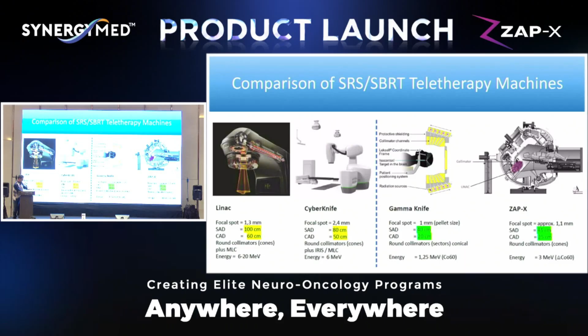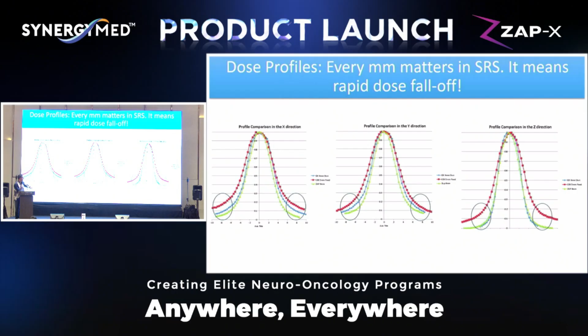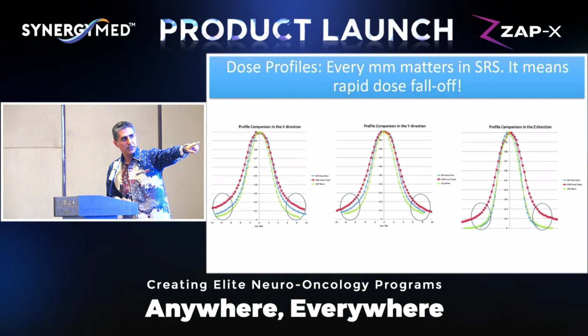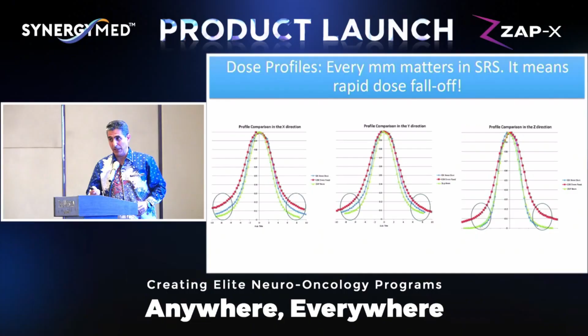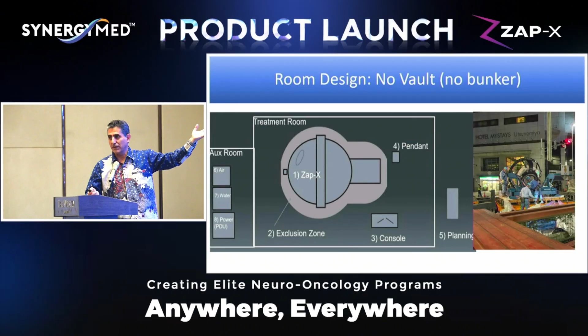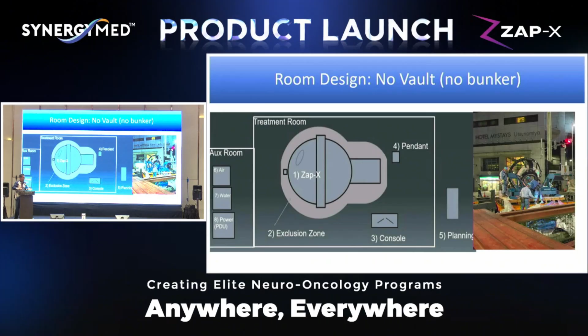The green one is the ZAP-X. The other blue one in the middle for the X direction is the Gamma Knife. The red one is the CyberKnife. You see the best profile, meaning the least collateral damage in the X and Y directions, comes from ZAP-X. Only in the Z direction can the Gamma Knife match the dose profile of ZAP-X. No need to say, there is no bunker, so I spare one bunker in my department for other devices.